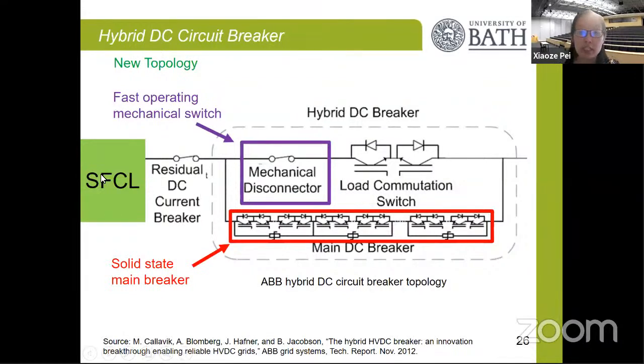What we want to achieve is to use the superconducting fault current limiter to limit the fault current level so that the hybrid circuit breaker is able to open reliably. Around this area, we're looking into 3 different topics. First, a new topology: do we have other new topologies around the hybrid circuit breaker? Secondly, the fast operating mechanical switch: how do we design the actuator to operate the mechanical switch?